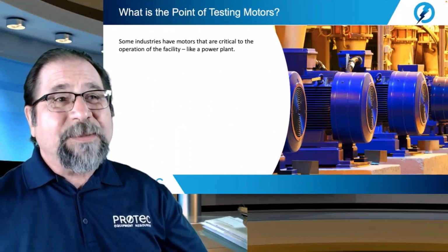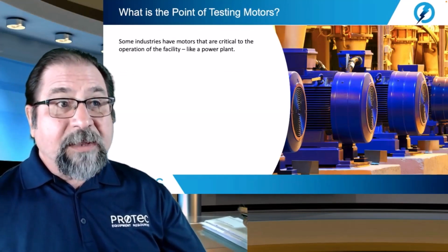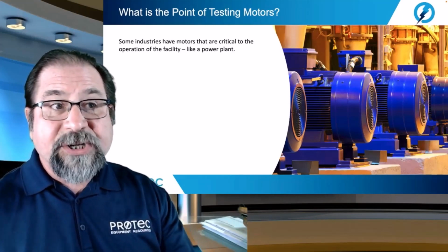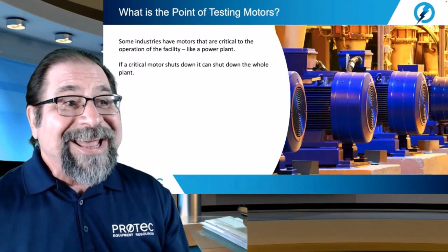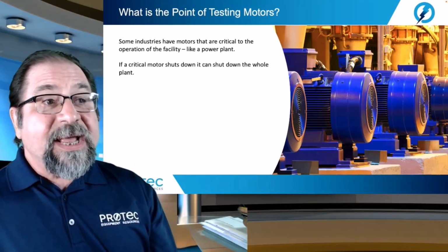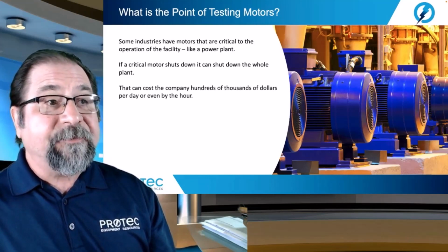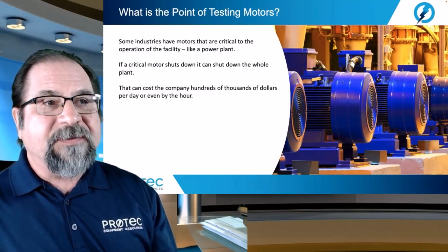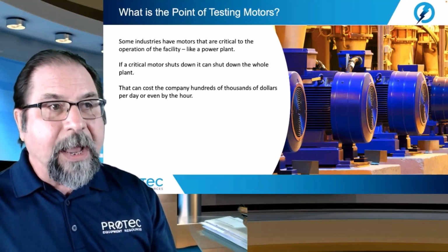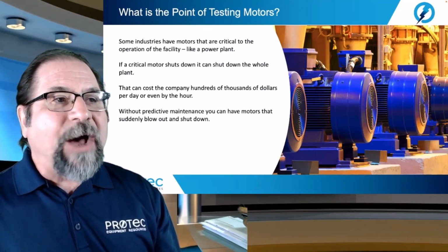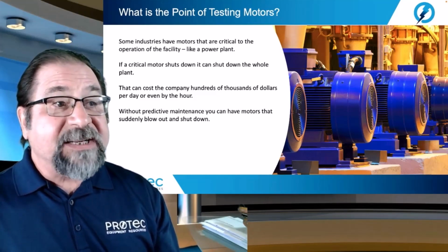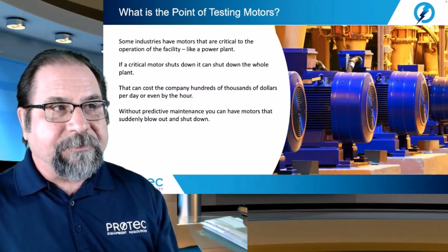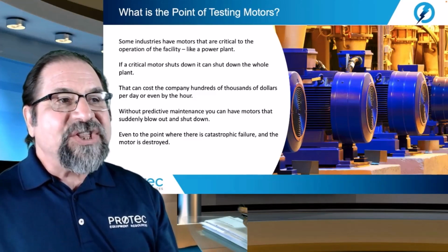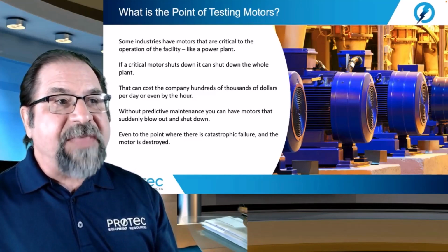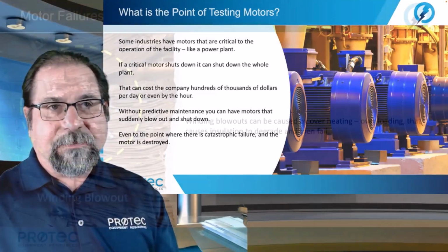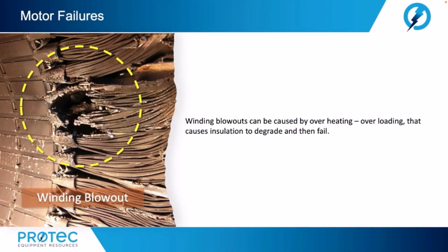Now, what is the point of testing motors? Well, some industries have motors that are critical to the operation of the facility, like a power plant. If a critical motor shuts down, it can shut down the whole plant. That can cost the company hundreds of thousands of dollars per day or even by the hour. Without predictive maintenance, you can have motors that suddenly blow out and shut down, even to the point where there is a catastrophic failure and the motor is destroyed. So let's talk about some of these motor failures.